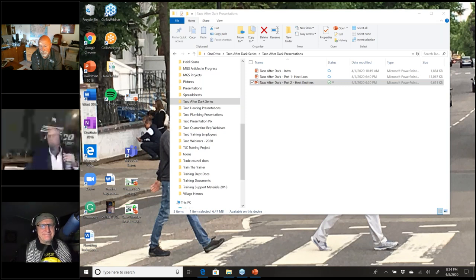But if you look at what John was showing earlier, when you look at anybody's baseboard output, they always list the 1 GPM and the 4 GPM. Just look, running four times more flow, does that give you less heat or does it give you more? And the answer always is more. Right. So that's kind of a wives' tale, and who knows where it came from. But again, that's not a license to overpump. We know enough nowadays and we have enough equipment available to us that we should never be overpumping, and we should sharpen our pencil when we size that pump, et cetera, et cetera.